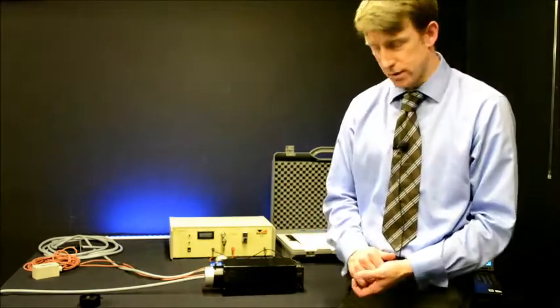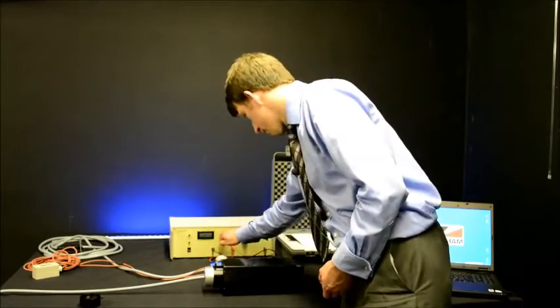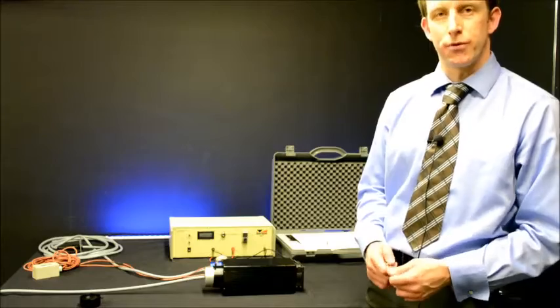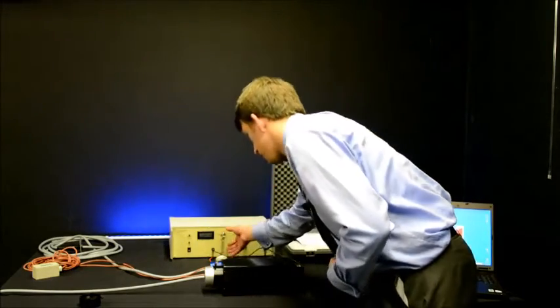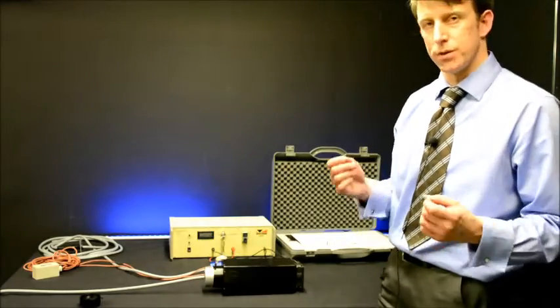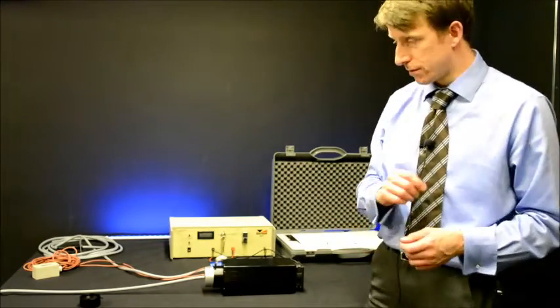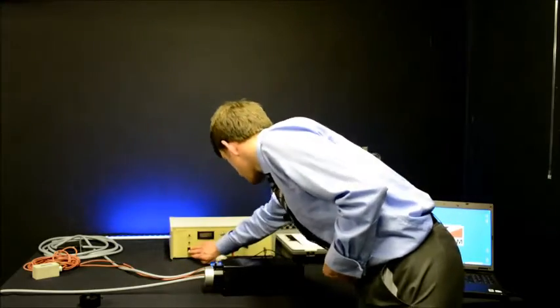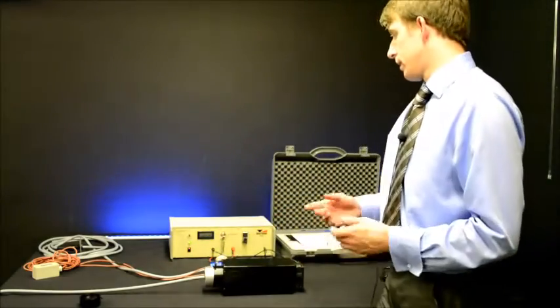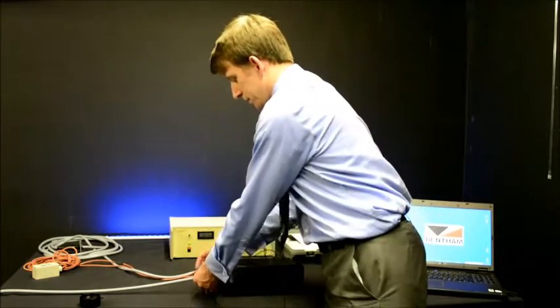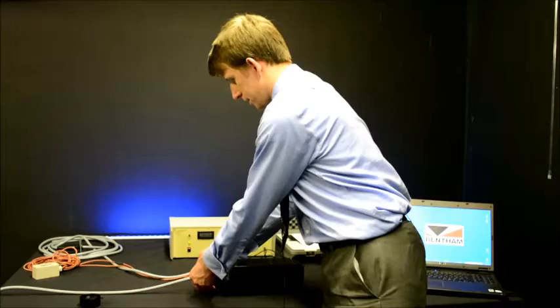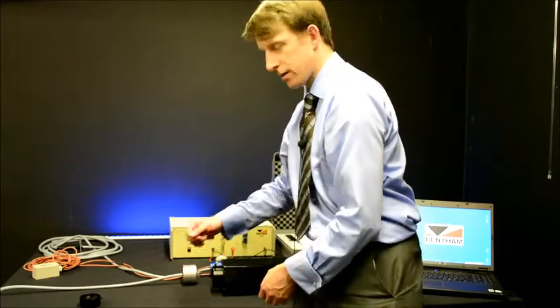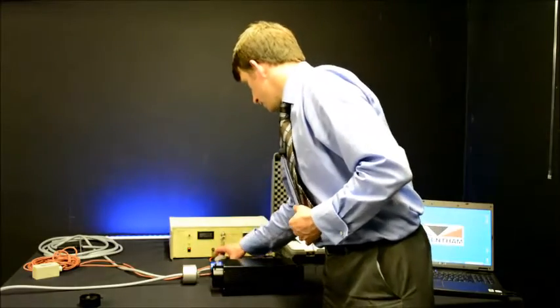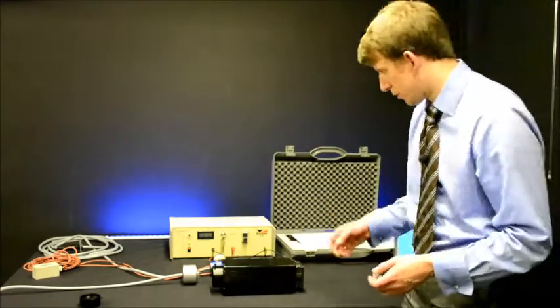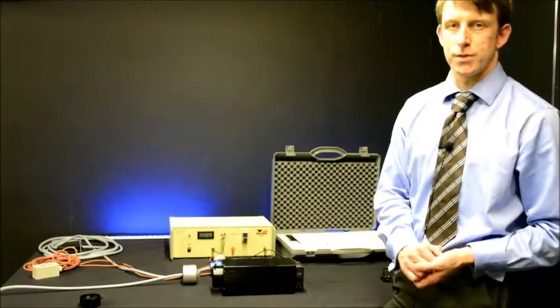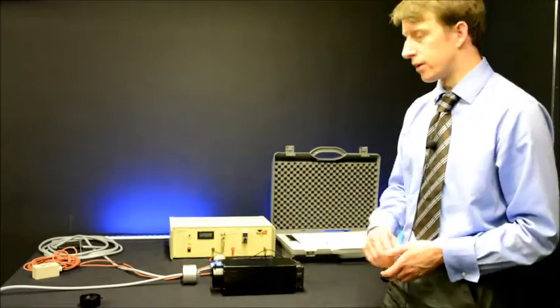To operate the CL6, one simply ensures that the etched arrow indicator points to 6.3 amps. I recommend withdrawing the key slightly to ensure that one doesn't inadvertently remove or change the current setting. At 6.3 amps, power on. And the lamp immediately powers on to the desired current and provides output. The front panel LCD will show voltage around -21, -22 volts. This is the compliance voltage across the lamp and the leads.